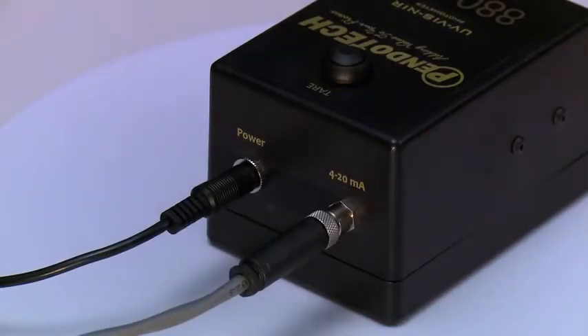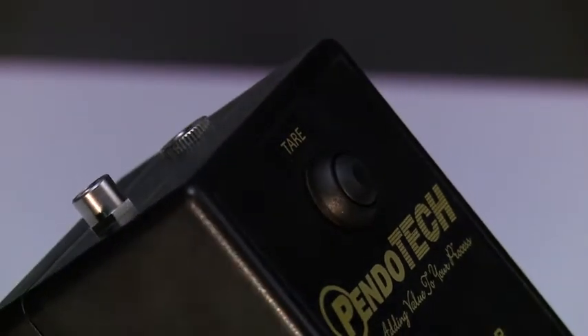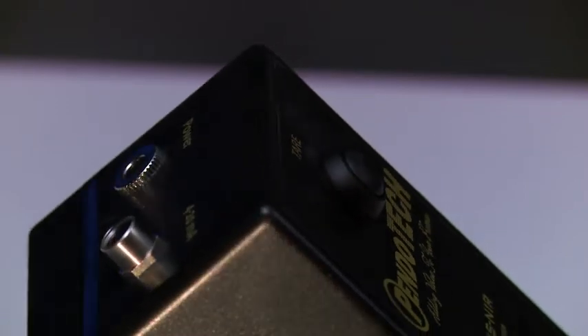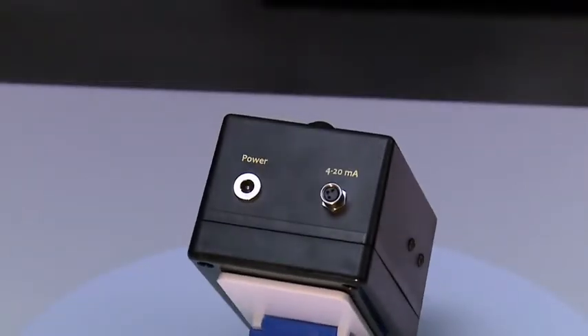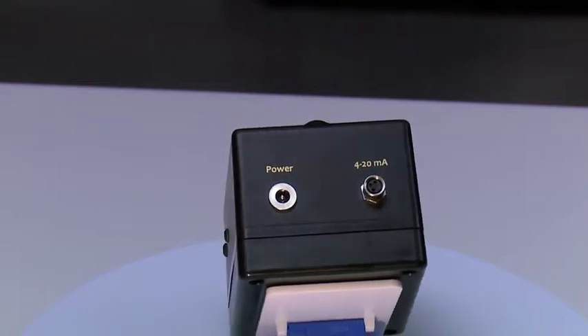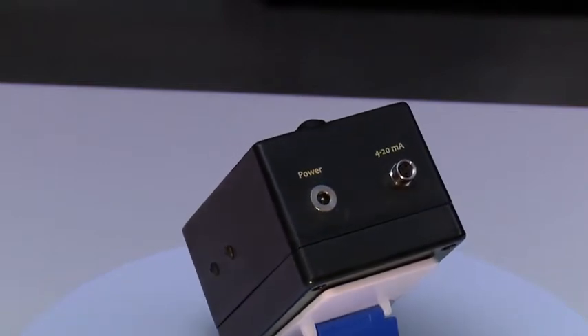On the lab version, the photometer comes with a 24-volt power supply that can be plugged into any wall outlet. The analog output is designed to be connected to an external device for viewing, logging, and trending. The 4 to 20 milliamp analog output is by default set to the range of 0 to 2 absorption units.